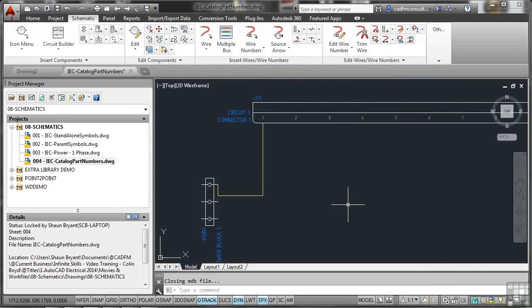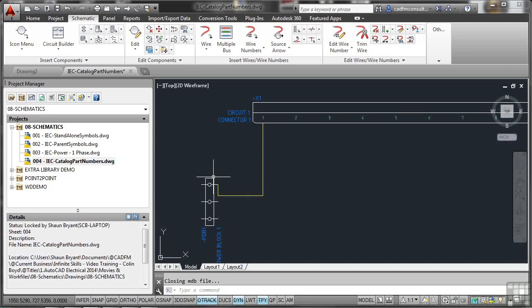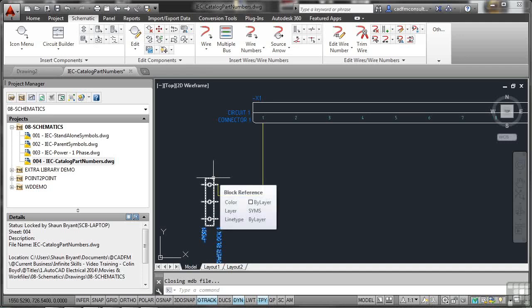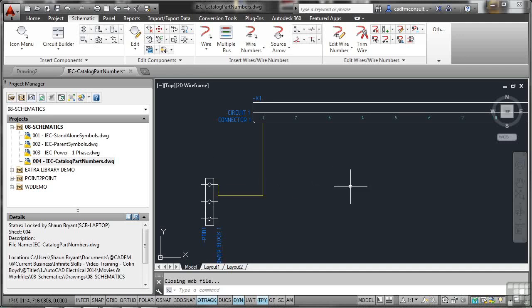So that is how you work with these catalogue part numbers. They're very important because they link to the bill of materials. When you're pricing up your project, once you've drawn it all up and all the circuits are linked and all the parts, components, and schematics are ready, you need to be able to go to that bill of materials and make sure that everything is linked to the project. In order to do that, everything needs a catalogue part number. So make sure that you check that. Unlike our little power block here, that hasn't got a catalogue part number. So what we need to do is make sure that it does have a catalogue part number by inserting the details into that dialogue box I showed you.